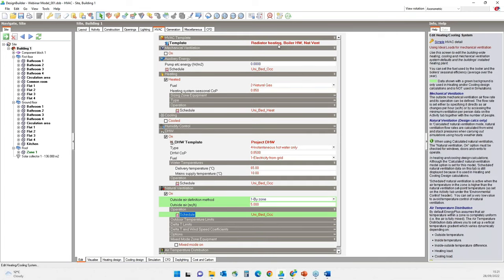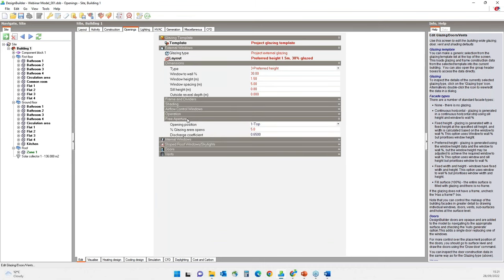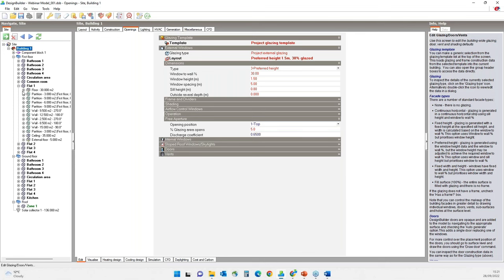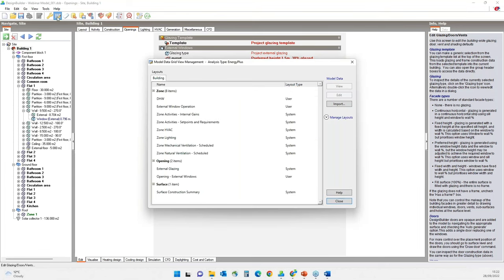I will leave the template selected to radiator heating, boiler hot water system with natural ventilation. For calculated natural ventilation, you must define the opening areas and operation controls. Here you can specify the total area of each window open to free airflow as a percentage of the total window area. I will assume 10% open area applies to all windows in the flats. You can make this change by navigating to individual blocks, zones, facades or openings. Most people find the best way to set this is using the model grid view tool, which can significantly speed up your data input.